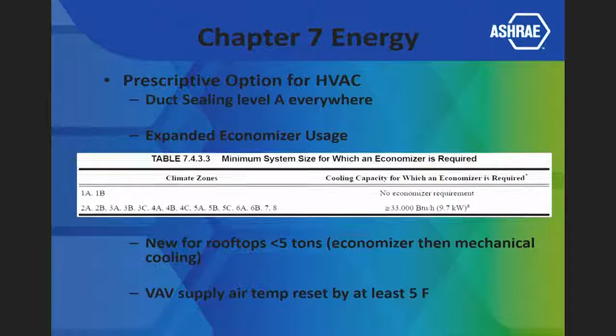There are also other things that deal with what's called reheat and fan. These are the two big areas that suck a lot of energy in our HVAC systems. If out of this box that air is always cold, and to satisfy the ventilation requirements I have to keep pumping air in here, I may have to reheat that air, make it a little warmer. You can do that a couple of different ways, but there are limits now on what you can and cannot do. And there are also limits on how much the fan back at the unit can consume in fan energy to deliver the air to all the spaces.